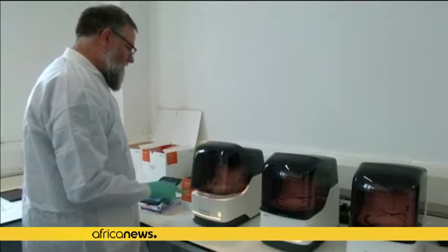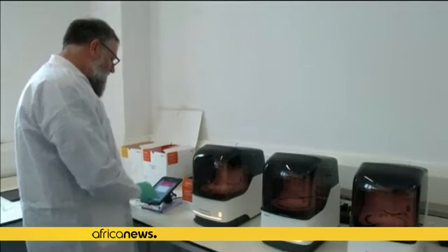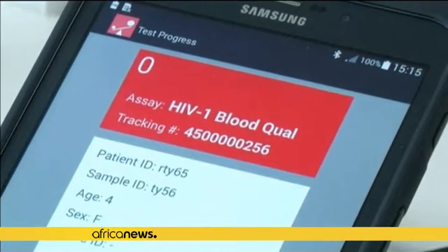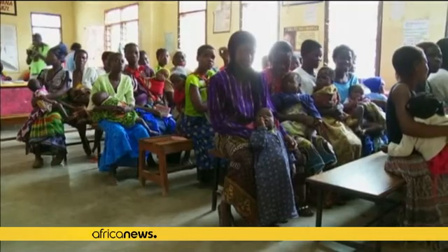Lee and her team demonstrated how the reagents and blood samples are loaded into the machine in separate individually shaped compartments. This is one of the cartridges, and it needs to be so intuitive that when you open it up and put it in, there's only one way you can put it — you couldn't put it wrong. We have simplified the procedure in such a way that I always say anyone who can cook can do it.